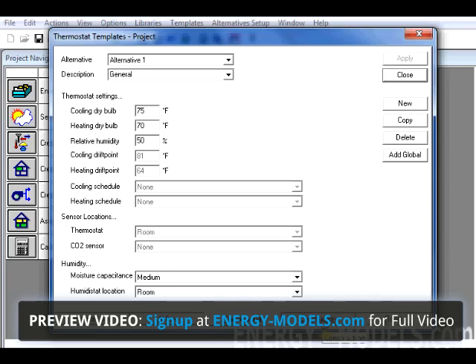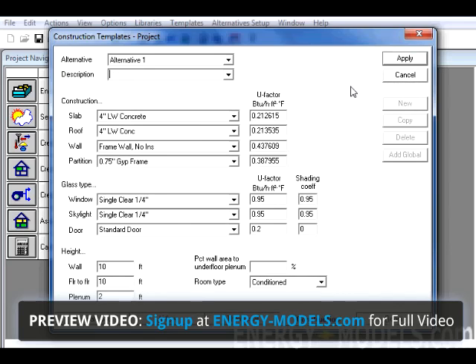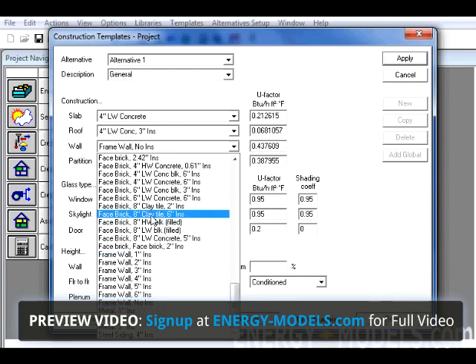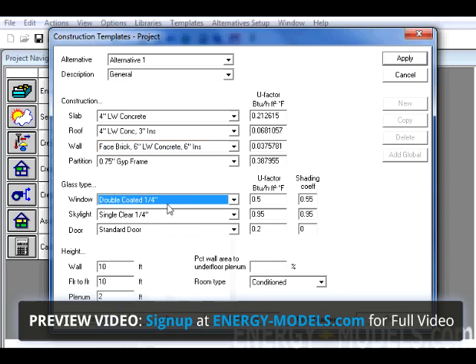The next details we'll enter are in the Construction Template. We'll click New, give it the Description General, and for the Roof, we're going to go down one and select 4-inch Lightweight Concrete, 3-inches of Insulation. For the Wall, we're going to enter Face Brick, 6-inches of Lightweight Concrete, and 6-inches of Insulation. For Windows and Skylights, we're going to enter Double-Coated 1-Quarter-Inch.